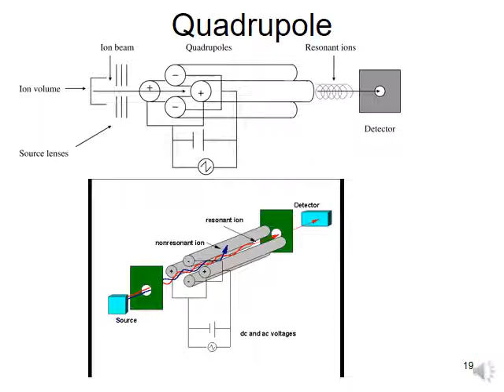This mass analyzer uses an electric field in order to separate the ions, and the ions are ejected into a vacuum chamber that contains four parallel metal rods. One pair of rods located opposite each other is positively charged, while the other pair is negatively charged. On top of the static positive and negative charge of the sets of rods, an additional plus-minus oscillation is imposed on the rods. The combination of oscillating positive and negative fields makes the ions in the vacuum chamber move in spiral patterns. At a given oscillation frequency, ions of either very large or very small mass spiral from the center and collide with the rods rather than reaching the mass detector at the end of the chamber.